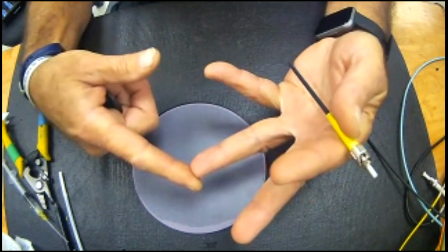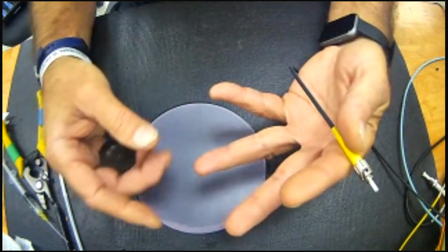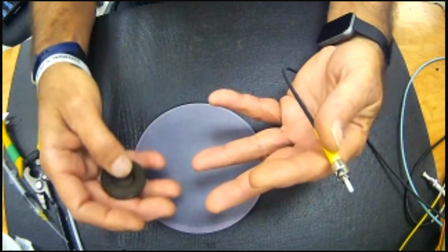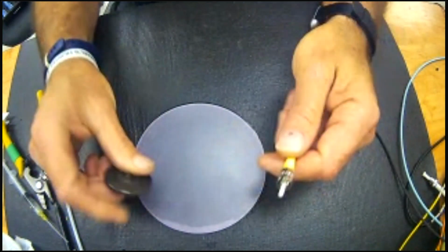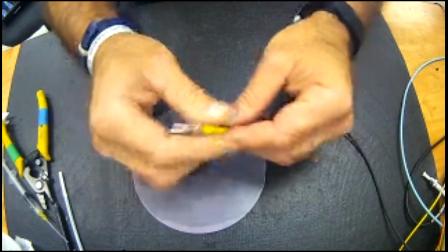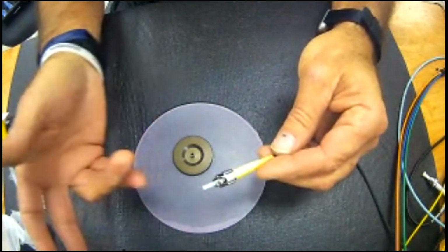The half is a weird, unusual thing, but it beats trying to go to an ultra film. If you want, you can skip the half and go straight to an ultra film, but it's completely unnecessary because you are hand polishing. This will yield you a tactical cable on a breakout design, 4 positions. You're going to spend about 10 minutes a connector.